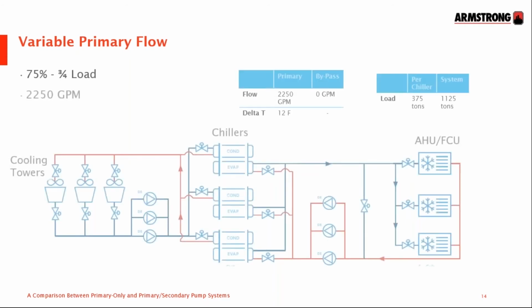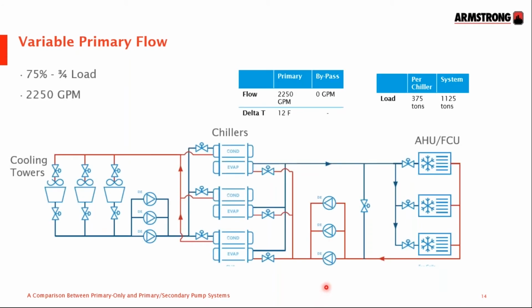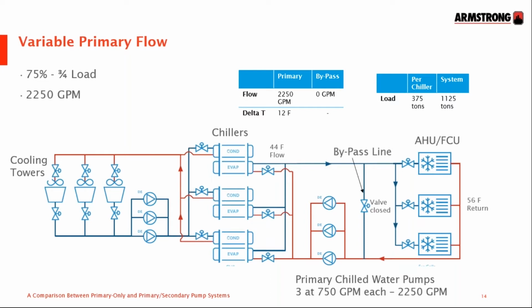At three-quarter load, the three main pumps will be slowed down from 1,000 gallons a minute to 750 gallons a minute, producing 2,250 GPM in total. That'll go through the coils once again, entering at 44 and leaving at 56, a 12-degree delta T, and that delta T remains the same across the chillers. So in this case we've got the same delta T but a reduced flow across the chillers, compared to the primary-secondary, where we had a reduced delta T and a constant flow rate through the chillers. The bypass line remains shut as before.